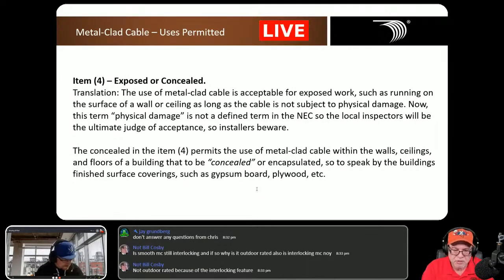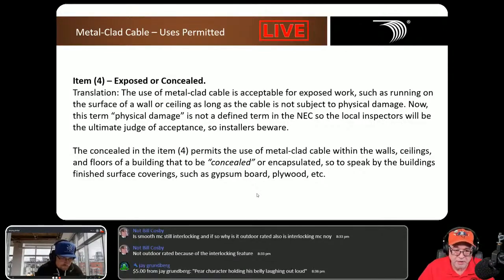And when it comes to physical damage, don't forget you have 300.4, which has got some rules you have to follow if it's subject to physical damage. So be aware of those rules if you're going to run your MC cable in a location where it could be subject to physical damage.